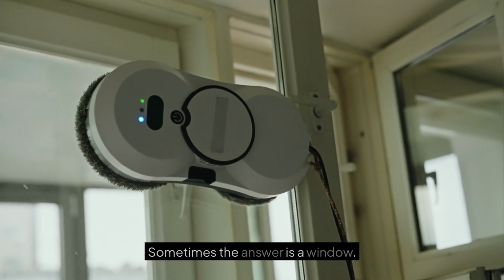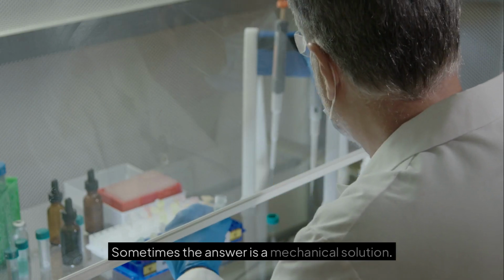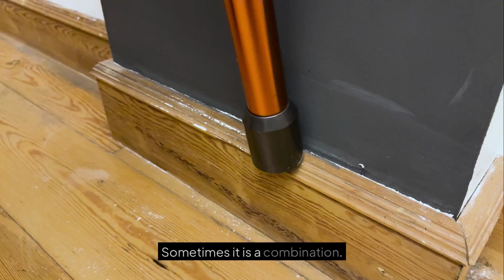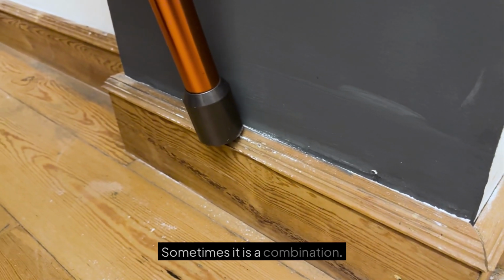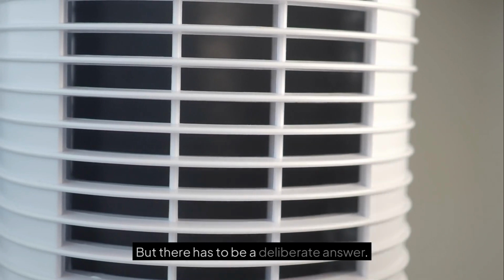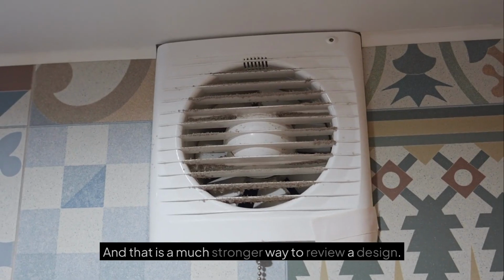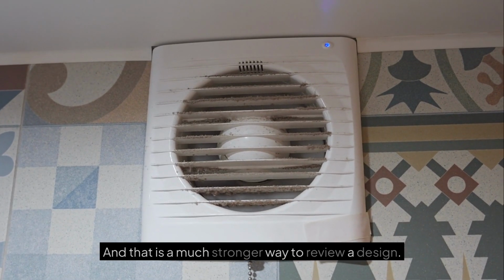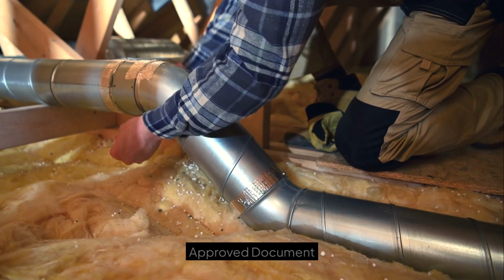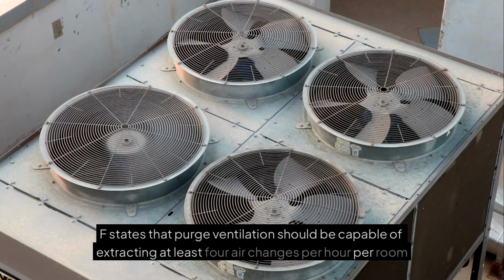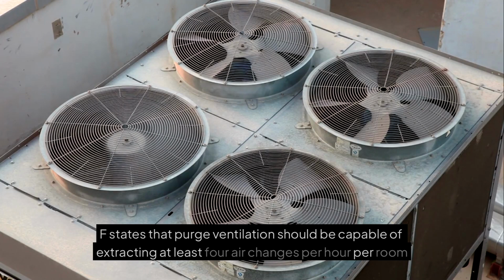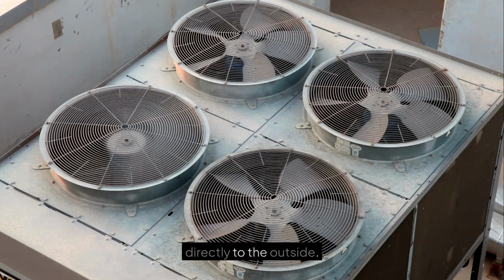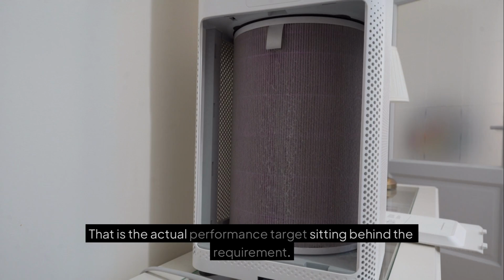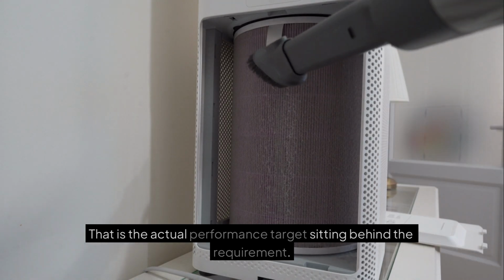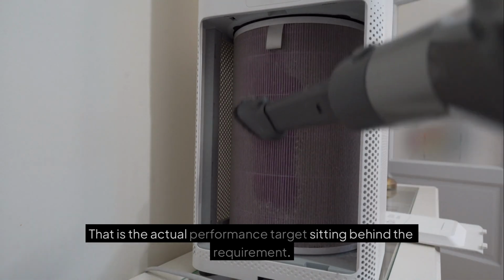Sometimes the answer is a window. Sometimes the answer is a mechanical solution. Sometimes it is a combination. But there has to be a deliberate answer. And that is a much stronger way to review a design. Approved Document F states that purge ventilation should be capable of extracting at least 4 air changes per hour per room directly to the outside. That is the actual performance target sitting behind the requirement.